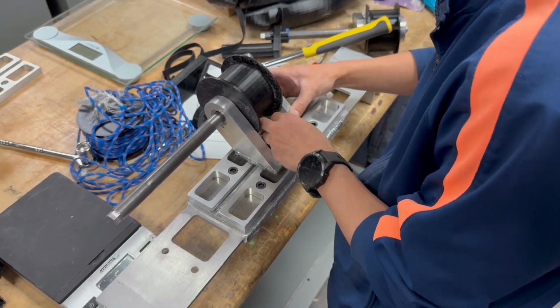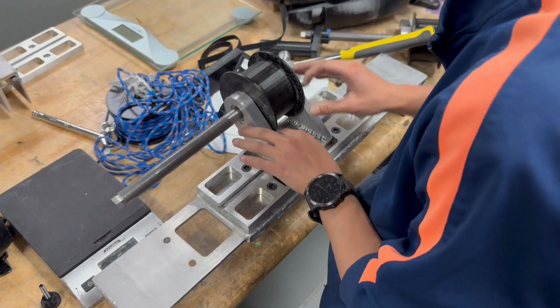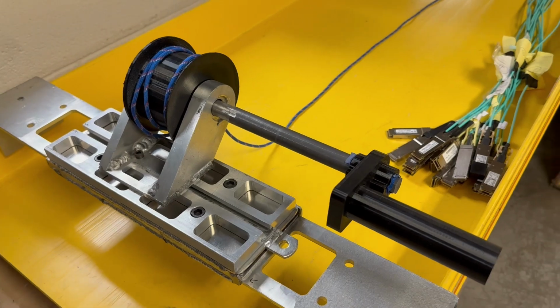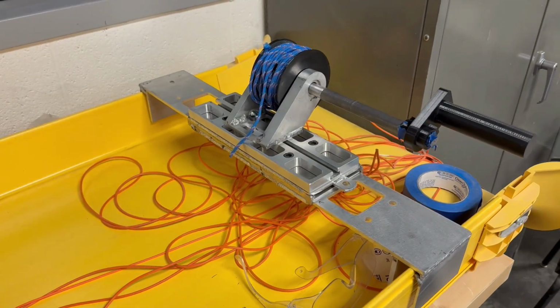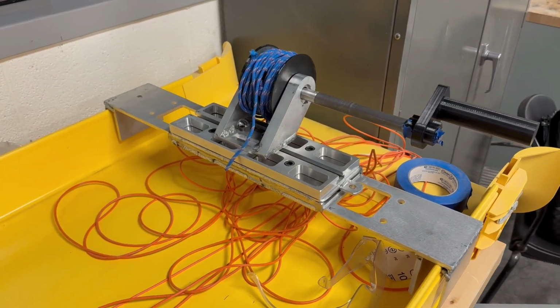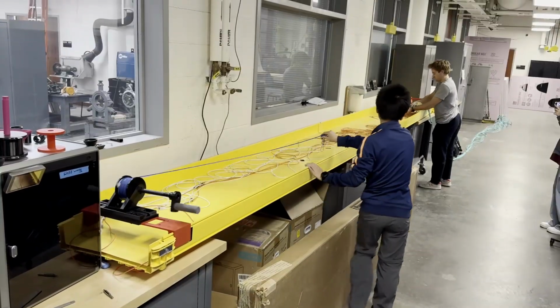the AOCs and the number of technicians needed to install the cables, which enhances the deployment process. Rather than physically dragging the cables by hand along a 40-foot section of cable trays, we designed a system that requires only 2 technicians to operate and reduces deployment time from 5 minutes to 2 minutes.